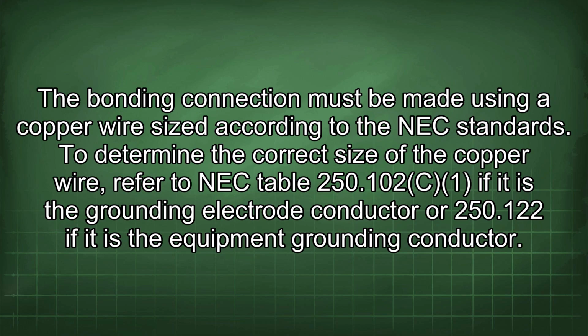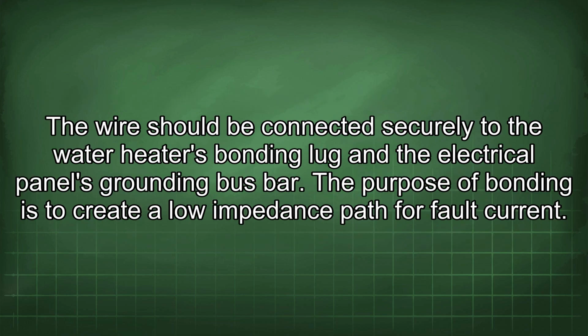To determine the correct size of the copper wire, refer to NEC Table 250.102 if it is the grounding electrode conductor, or 250.122 if it is the equipment grounding conductor. The wire should be connected securely to the water heater's bonding lug and the electrical panel's grounding bus bar.